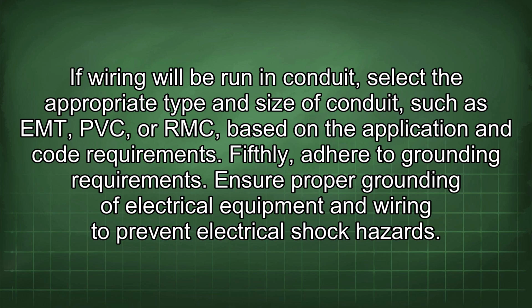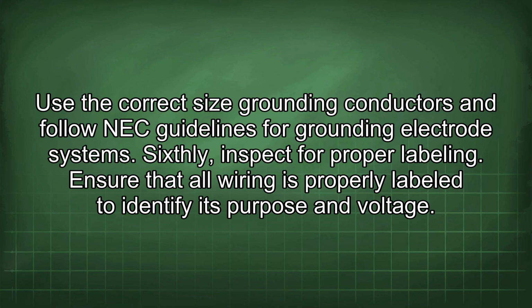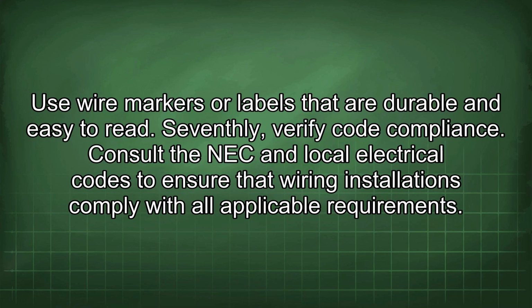Fifthly, adhere to grounding requirements. Ensure proper grounding of electrical equipment and wiring to prevent electrical shock hazards. Use the correct size grounding conductors and follow NEC guidelines for grounding electrode systems. Sixthly, inspect for proper labeling. Ensure that all wiring is properly labeled to identify its purpose and voltage. Use wire markers or labels that are durable and easy to read.